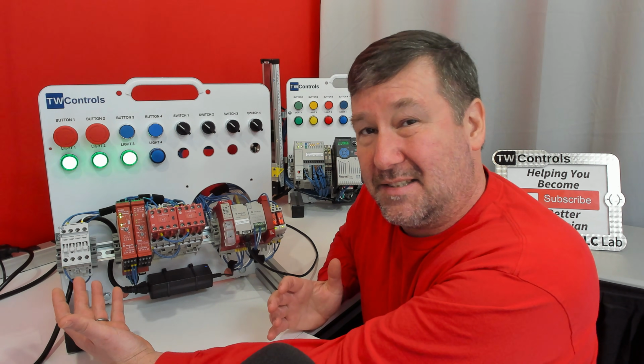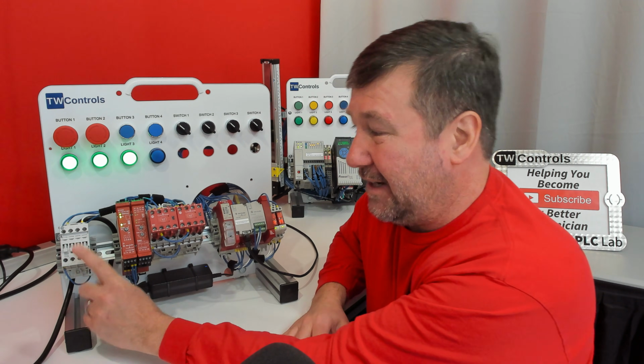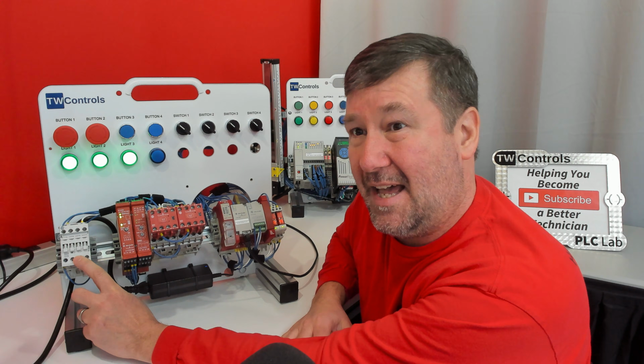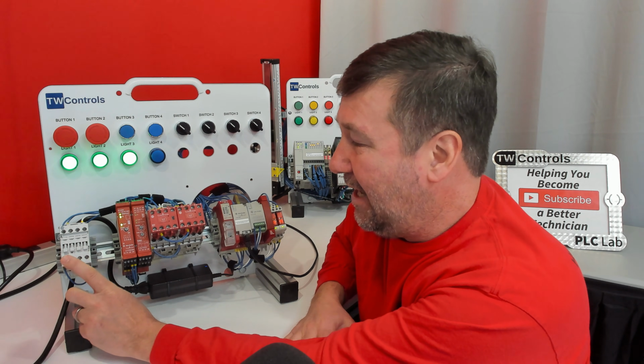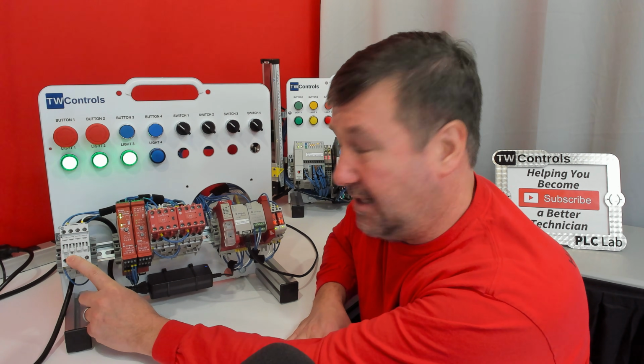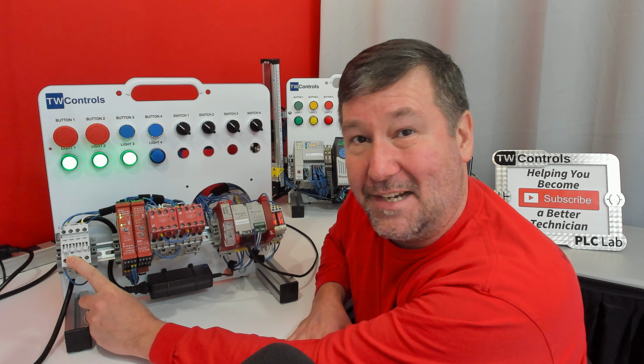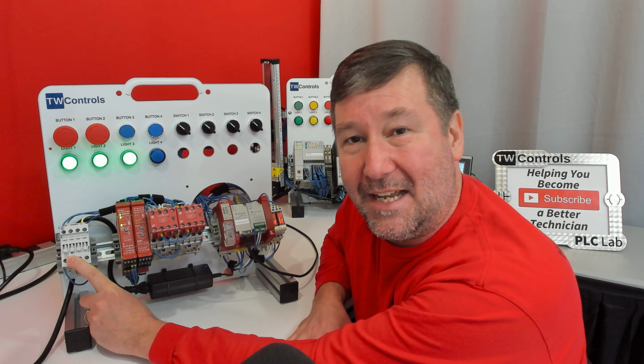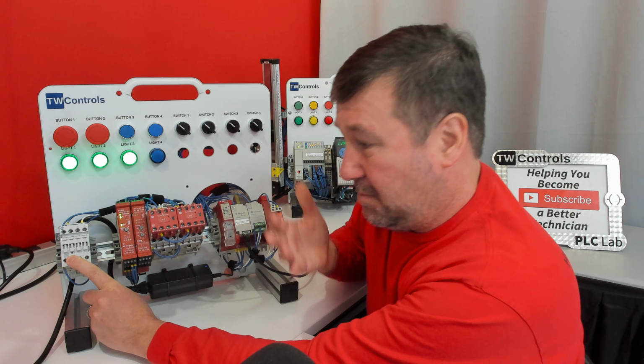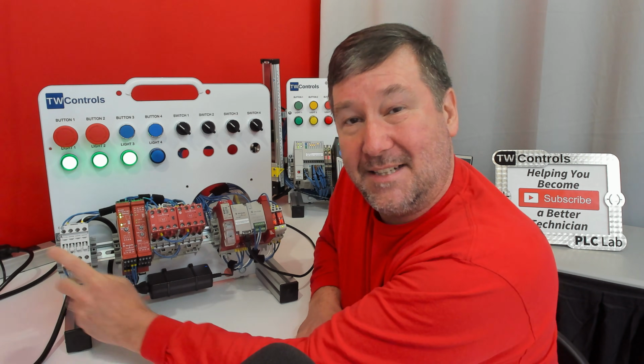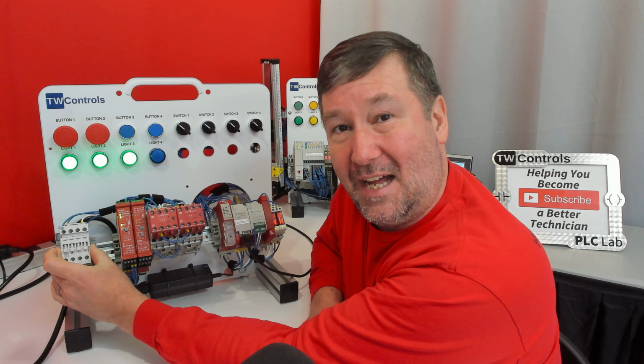Now the other side is equally as dangerous a failure. Arguably, I would say this is probably more commonly a failure, especially on systems that people haven't thought about safety: we have a single contactor here, and chances are we had a 9 amp load, so we went and got a 9 amp contactor, not knowing the difference between amps and horsepower. And so we are overloading this contactor.